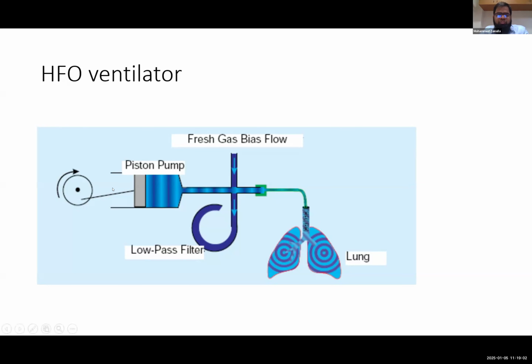But now other ventilators are using different mechanisms, like a diaphragm in the Dräger, and a reverse jet in the SLE ventilator. But overall, the mechanism is that you are pushing forward using the piston pump. How far you push will determine your amplitude, how deep you push and how much you retract. How much time it takes to push forward is the inspiratory time, and the time it takes to push backward is the expiratory time. So inspiratory and expiratory time and amplitude are determined by this piston pump, how deep it is pushing and how much time it takes for these movements.